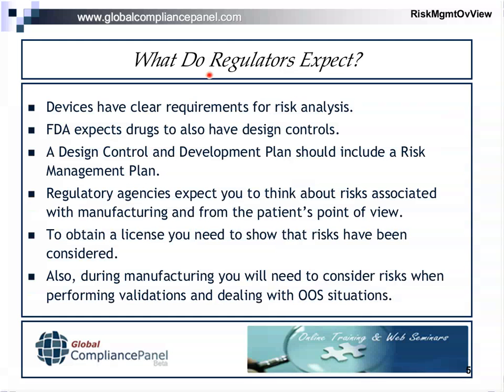What do the regulators expect? For the device people, it's fairly clear — there are clear requirements for risk analysis. But for drugs, FDA has recently brought in the expectation that you have design control. This applies at early stages or with a new product, but even for old products, they'd like you to go back and look at the design of the product, your development plan, and this should include a risk management plan. Even if you have an old product, you still want to go back and conduct a risk management review.